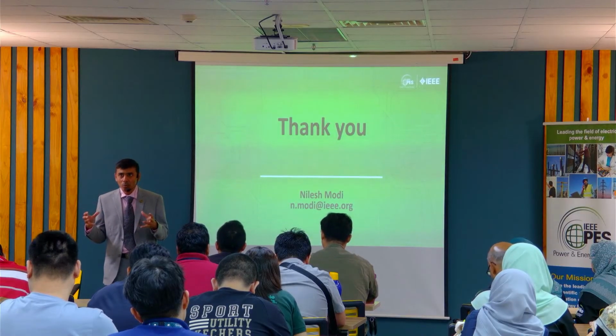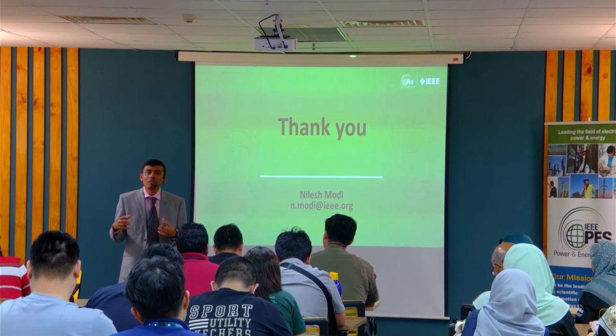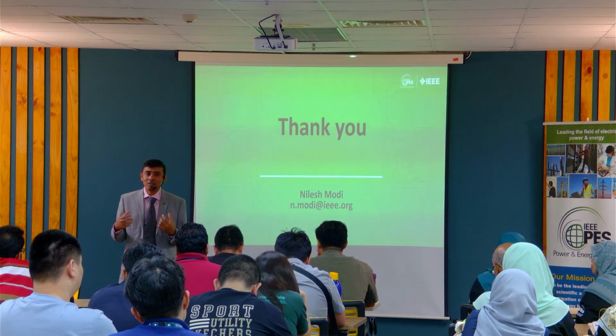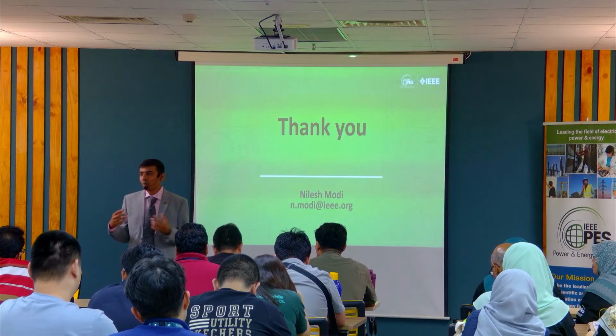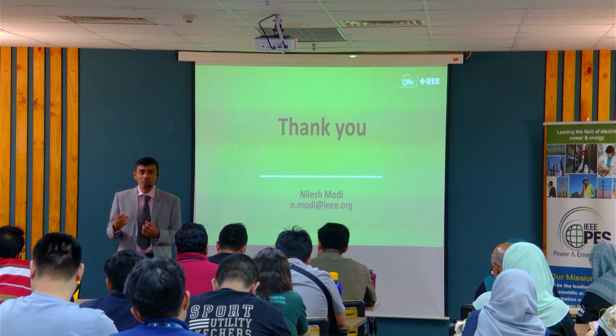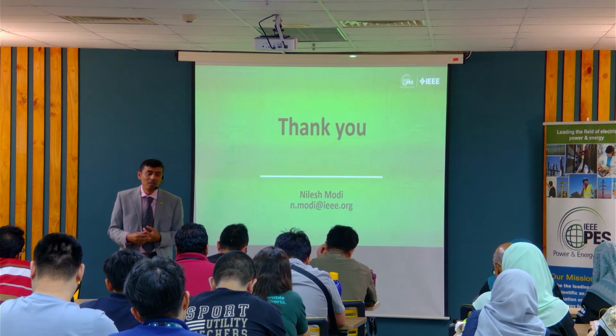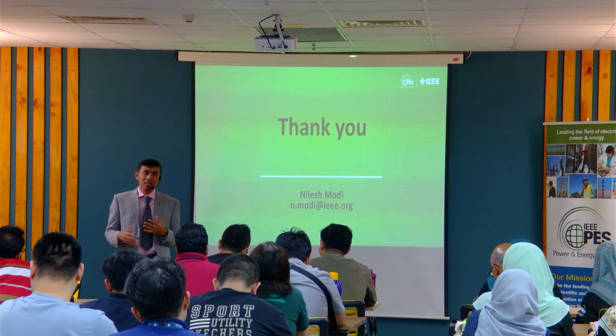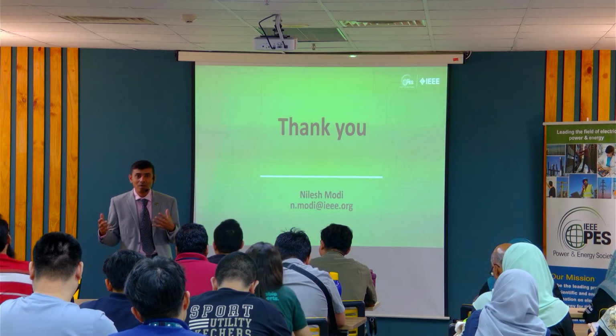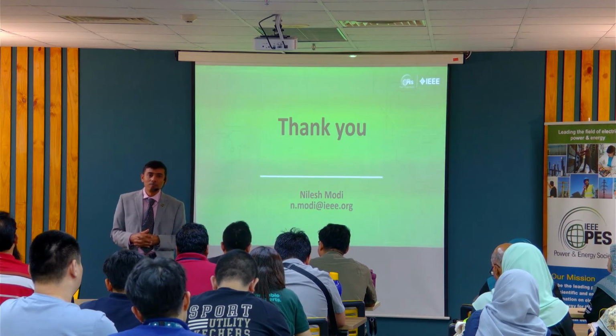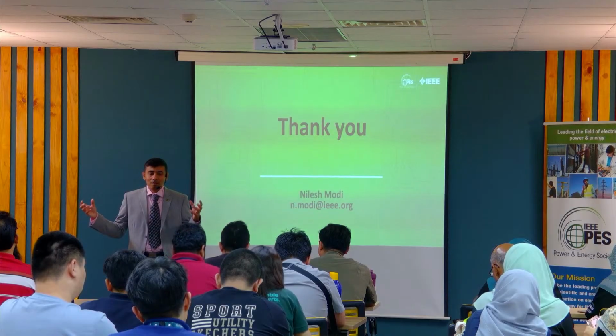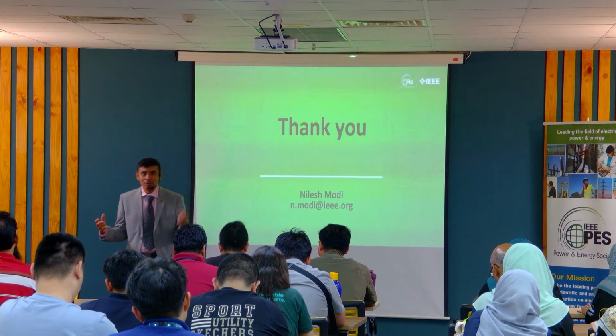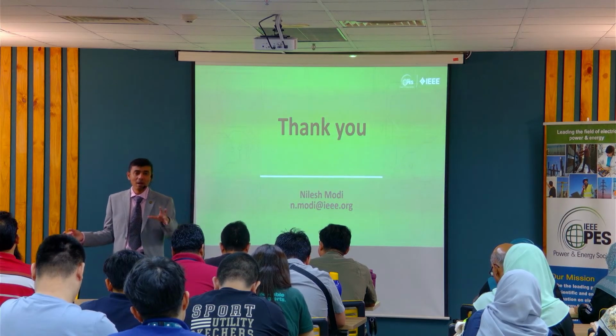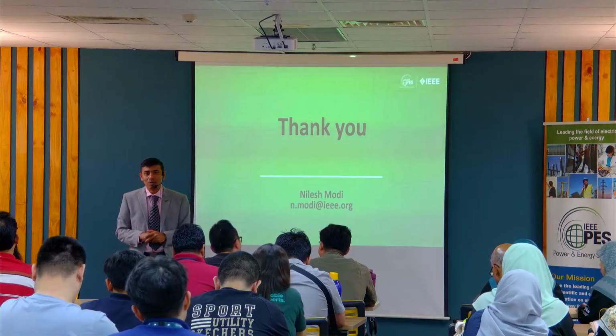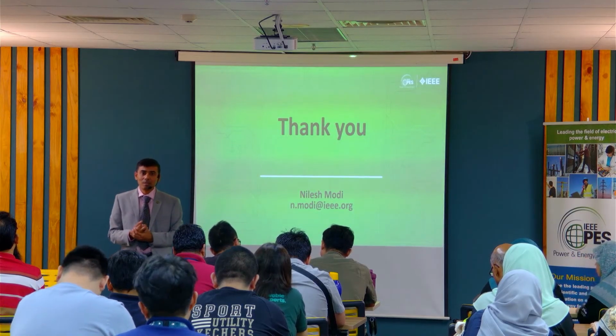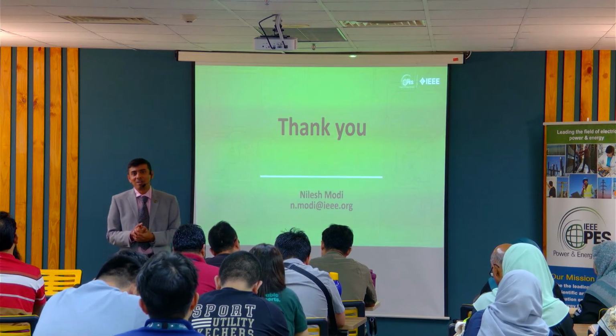As you have more concentration of IBR, that's where you need to seriously start thinking about EMT modeling, or at least a modeling which can capture those phenomena. If you've got a system which is very high synchronous, your SCR levels are really, really high, unlikely that a good manufacturer plant would give you an issue. But as soon as you start looking at close proximity of IBR, one wind farm, next door another wind farm, and then a solar farm coming in, few batteries coming in, that's where you start looking at EMT modeling. So it's kind of an educated guess you need to make. There's no rule of thumb that this percentage is something where you start looking into EMT.